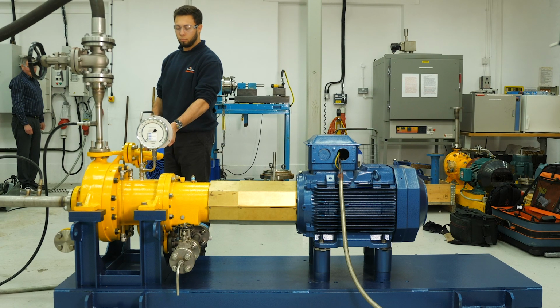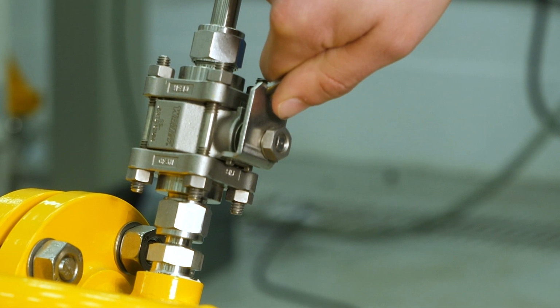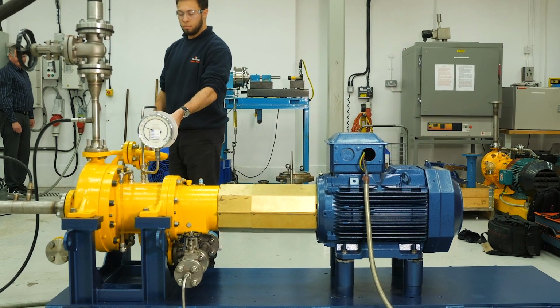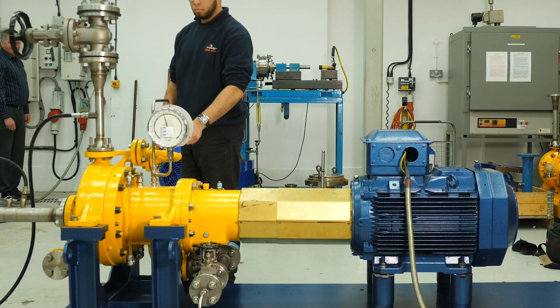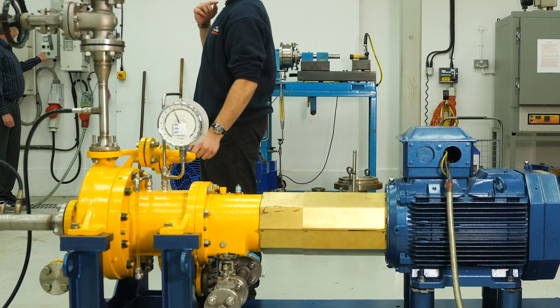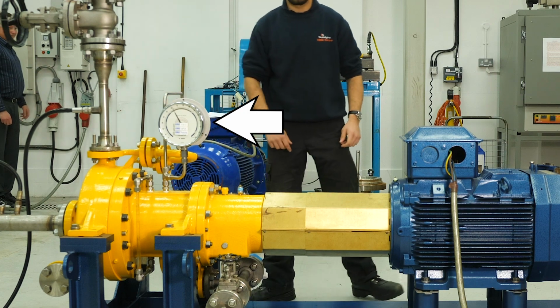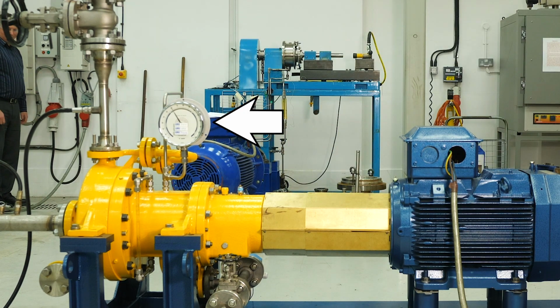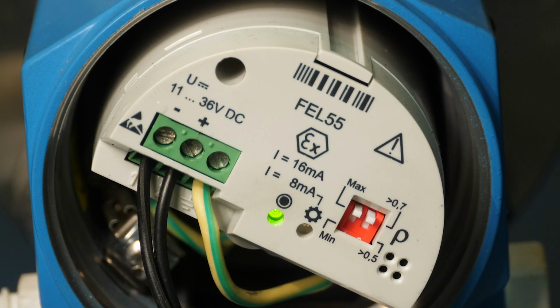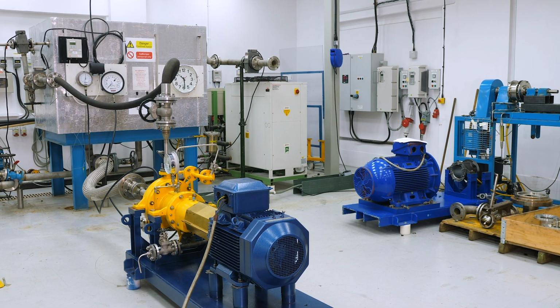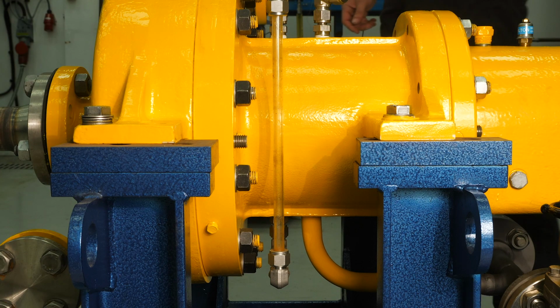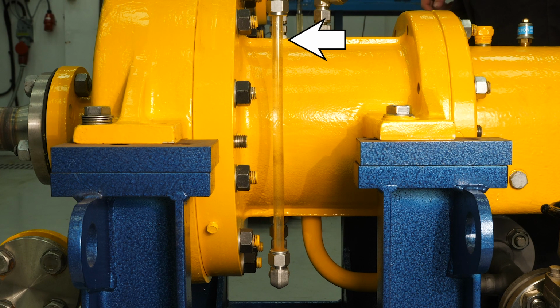A pressure boundary breach is simulated by opening the feed pipe valve of the test pump. Water or process liquid fills the secondary pressure housing, which increases to the discharge pressure. The liquid sensing probe detects the presence of liquid in the secondary pressure housing and is set to immediately stop the pump. A tube connected to the coupling housing for this test shows the level of the process liquid in the coupling housing.